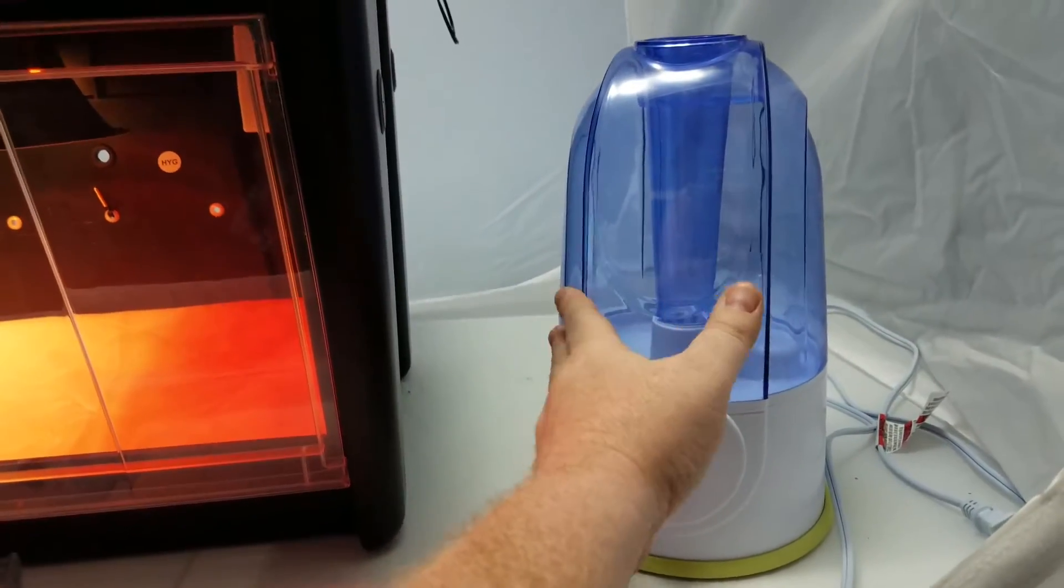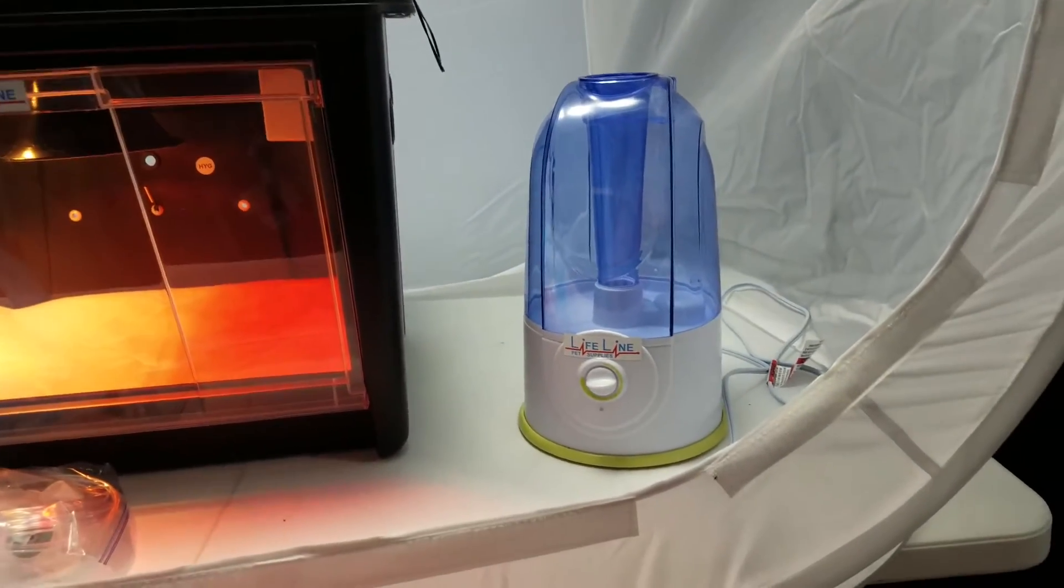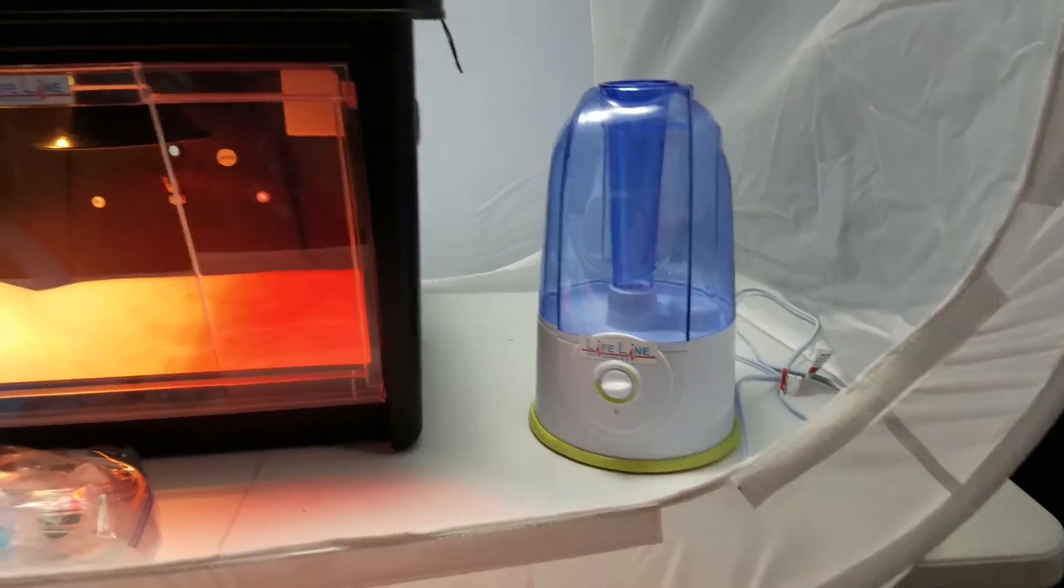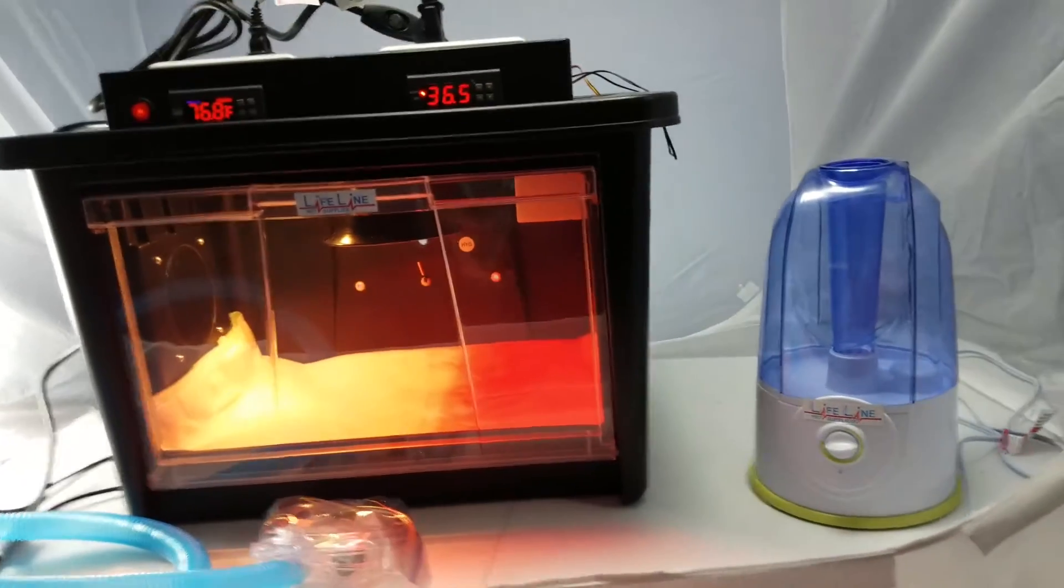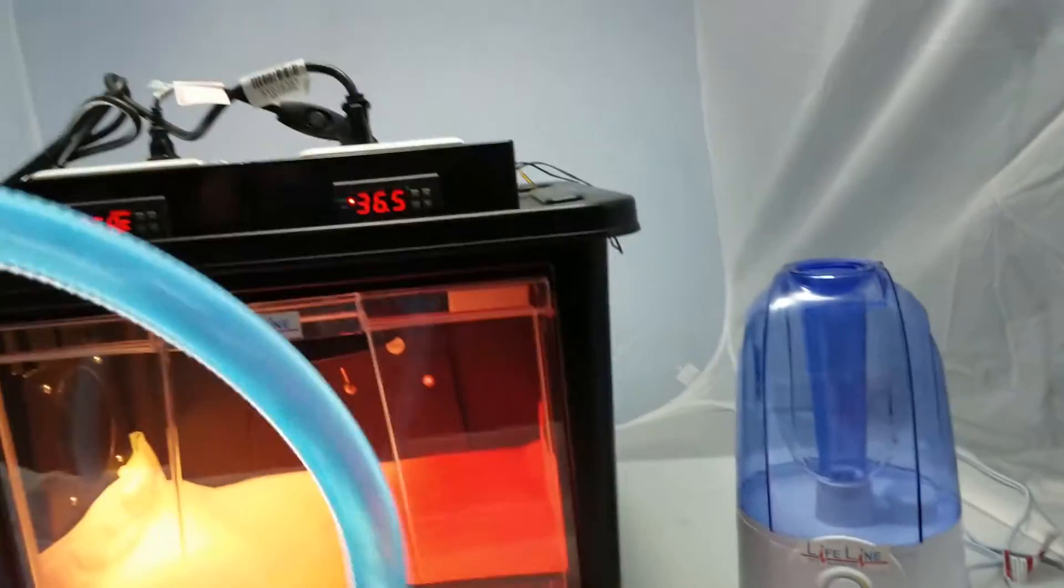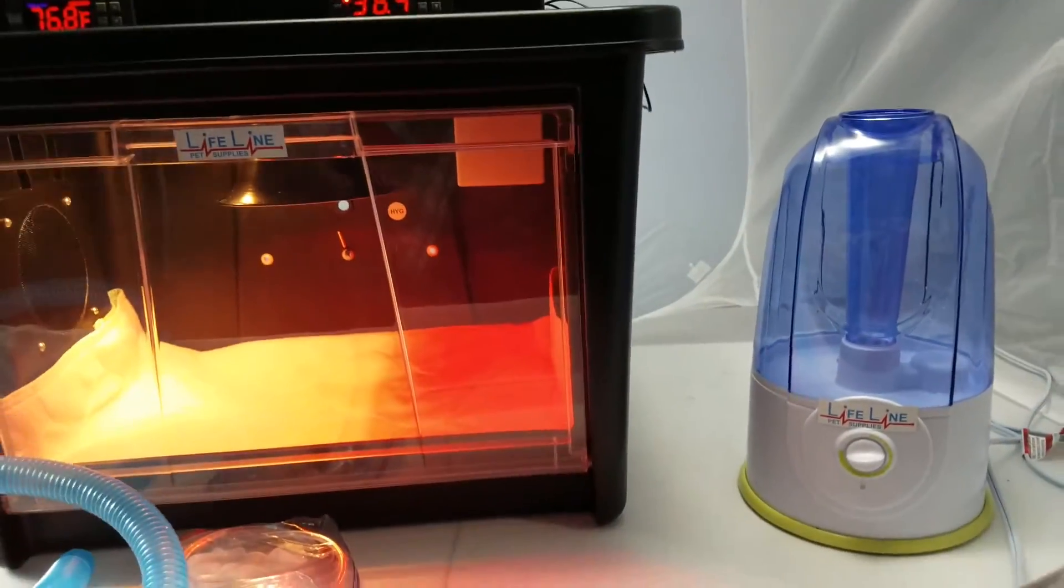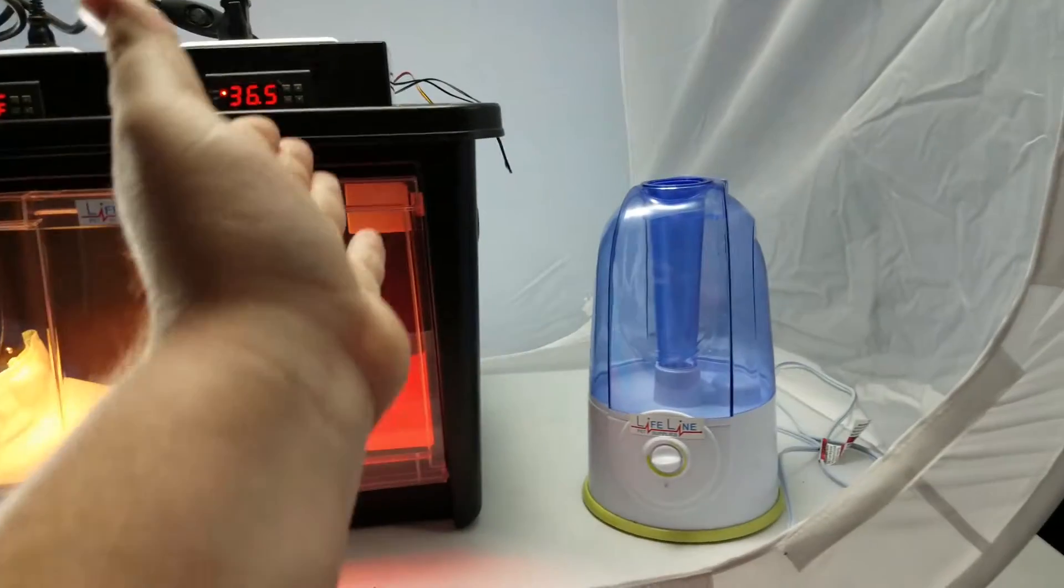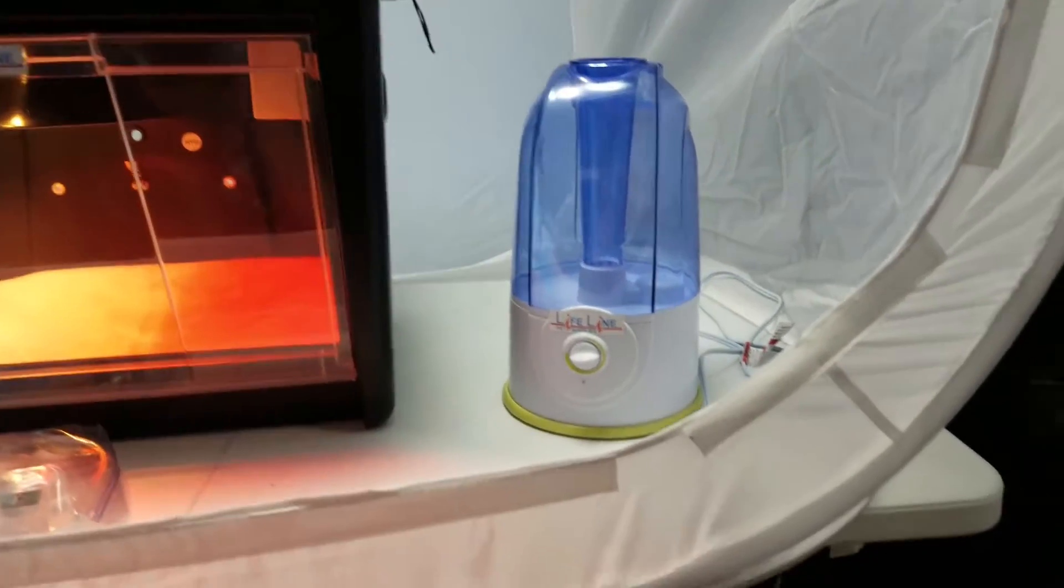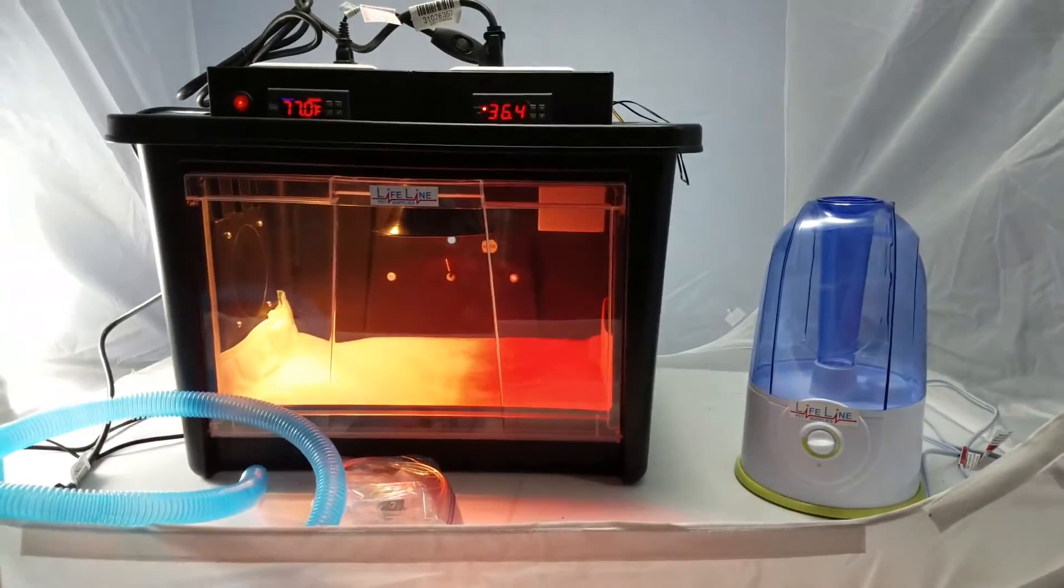So we actually recommend putting this pump on the floor next to where you're going to keep the incubator and keep this blue tubing running at a decline so it has no low spots in it back to the humidity pump.